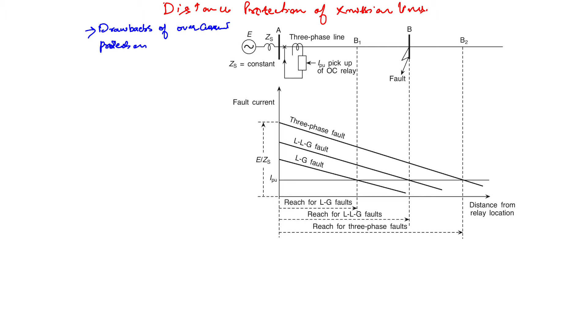This is not a desirable trait for a protection system. Now, from this diagram, you will see that if the overcurrent relay pickup setting is equal to I per unit, then it gives the reach up to bus B, assuming the source impedance equals ZS2. Then it underreaches to point B1 with the source impedance ZS1 and overreaches to point B2 in that very case. Again, this is not a desirable trait. So it will underreach and overreach depending upon the type of fault and the source impedance.